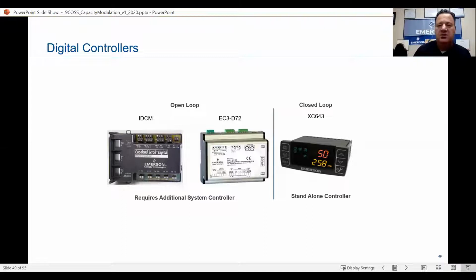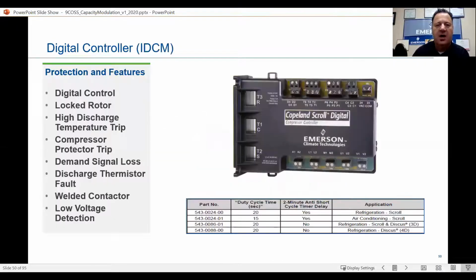But what they're saying here is it doesn't need a controller. All it needs is this standalone controller, and that's what we're referring to as a closed loop. Now, on the IDCM board, some of the protection features: a digital control, obviously, locked rotor, high discharge temperature trip, compressor trip, demand signal, discharge thermistor fault, and then a welded contactor.